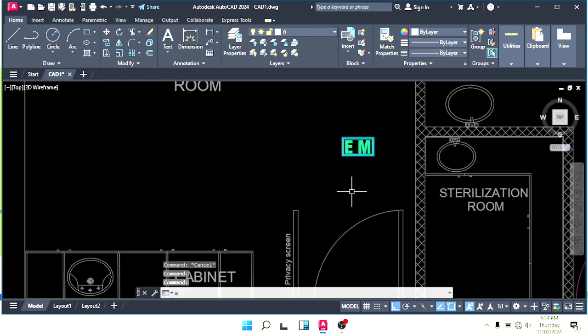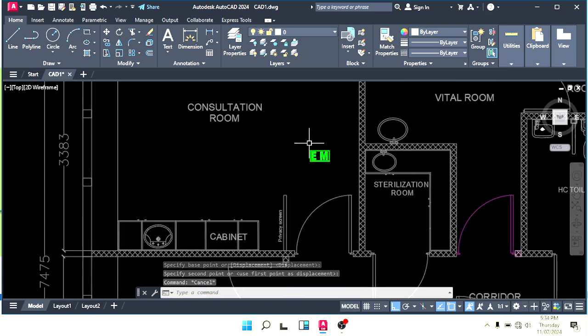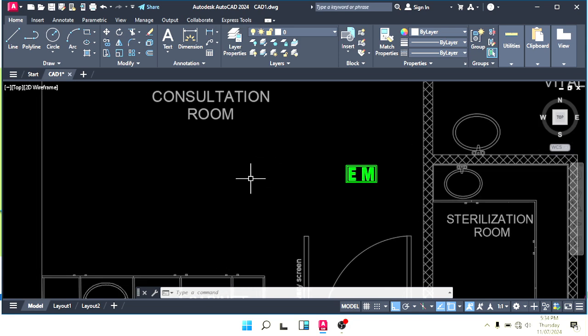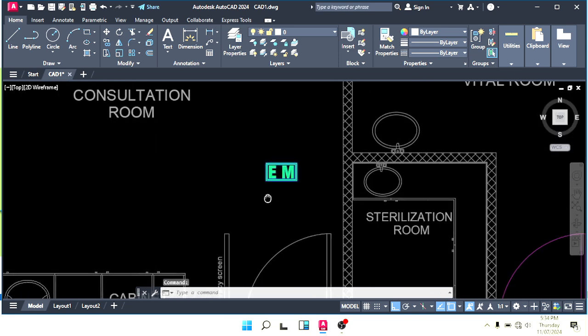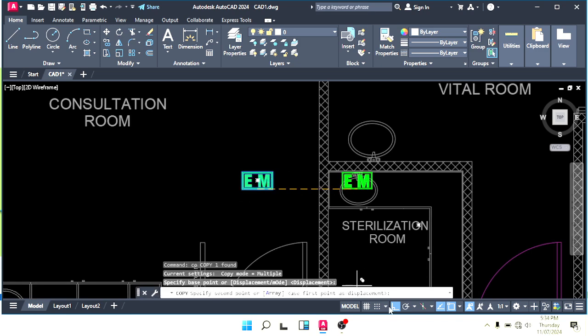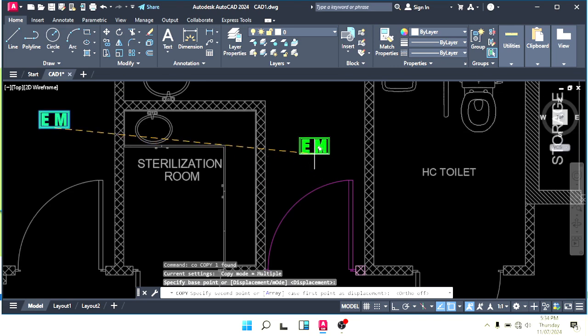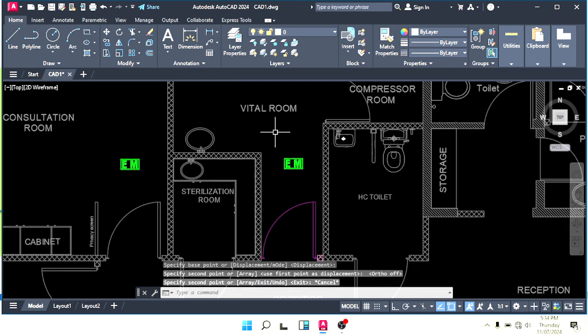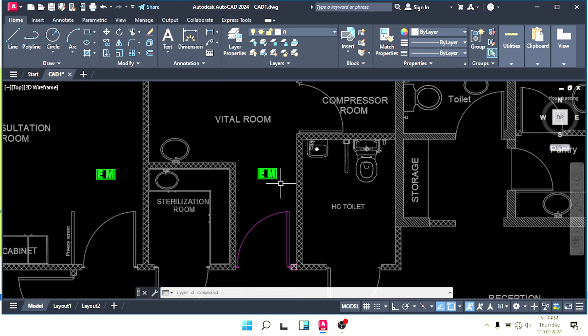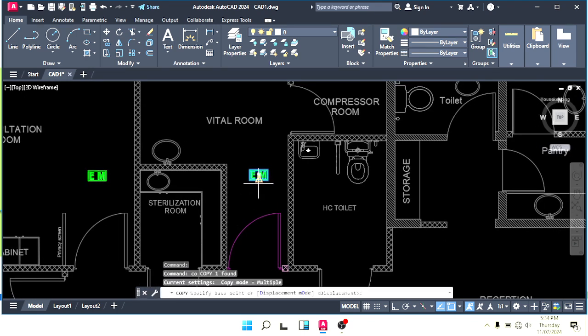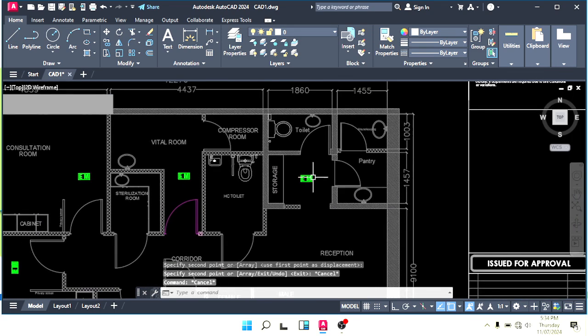We will check in the RCP layout exactly where it will go — it depends on what kind of ceiling they have. If it's 60x60, it will be in the center. This is the vital room — make one emergency light here, which will cover this area and this area as well, near or towards the door. Then make one emergency light here. In the storage, no need for an emergency light.